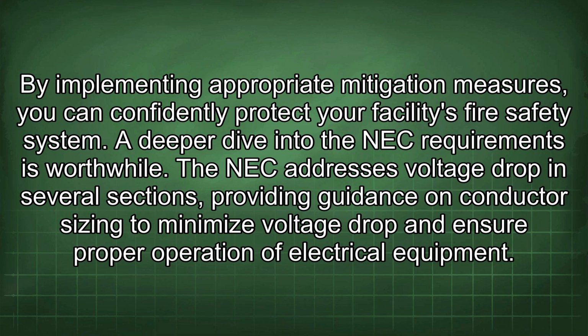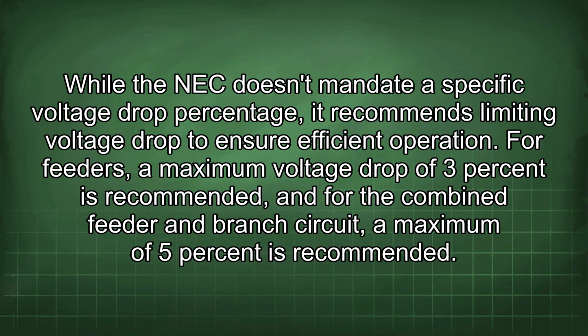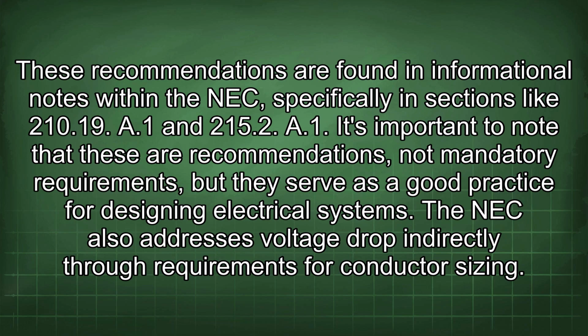A deeper dive into the NEC requirements is worthwhile. The NEC addresses voltage drop in several sections, providing guidance on conductor sizing to minimize voltage drop and ensure proper operation of electrical equipment. While the NEC doesn't mandate a specific voltage drop percentage, it recommends limiting voltage drop to ensure efficient operation. For feeders, a maximum voltage drop of 3% is recommended, and for the combined feeder and branch circuit, a maximum of 5% is recommended. These recommendations are found in informational notes within the NEC, specifically in sections like 210.19(A)(1) and 215.2(A)(1).